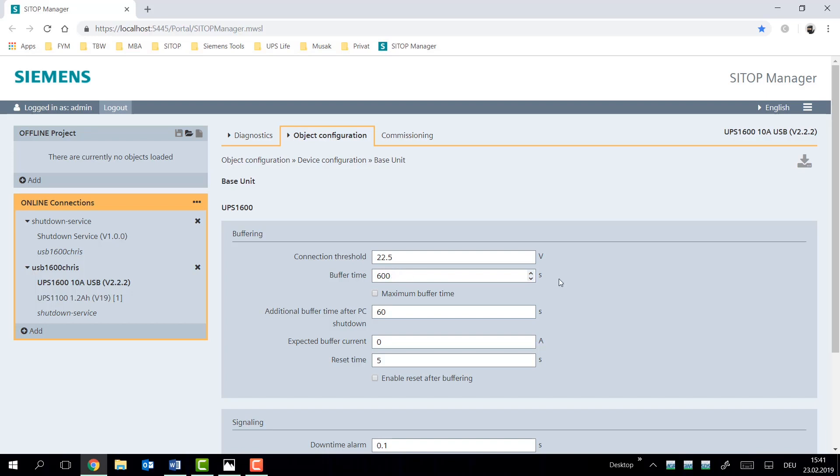In such applications it's important to restart the system with a charged battery, but if the system has been maximum depleted, then we have to wait for the 85% charge of the batteries before the system is, in most cases, considered viable. Limiting the buffering time is actually very common for most people to set.